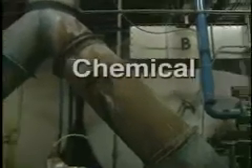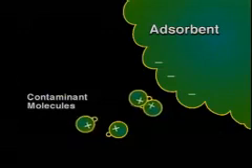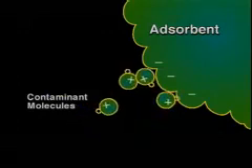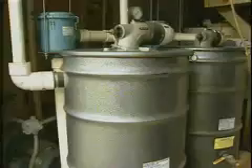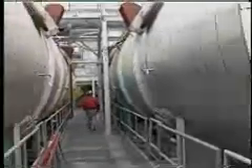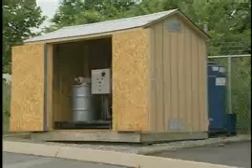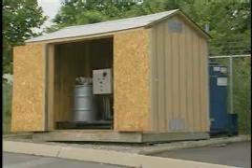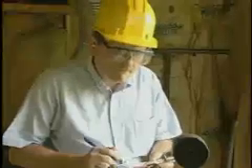There are two types of adsorption processes: chemical adsorption and physical adsorption. Chemical adsorption is not used often in air pollution control systems because of the difficulty in regenerating the adsorbent material. In physical adsorption, the contaminant molecule is lightly held to the surface of the adsorbent by weak electrostatic forces, and the adsorbent material can be easily regenerated. There are two types of activated carbon systems: those that regenerate on site and those that do not. The two most common industrial adsorbers are a fixed bed design that regenerates on site and a fixed bed design that does not regenerate on site, often referred to as a carbon drum. Today we will be seeing units of both types.